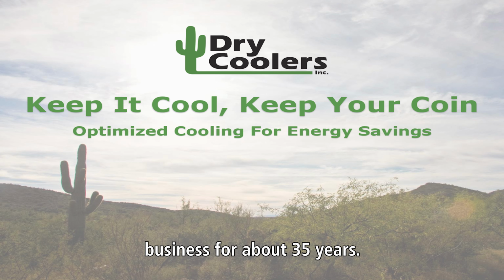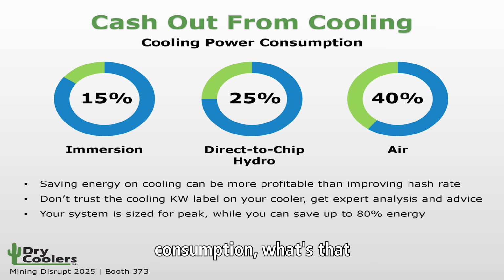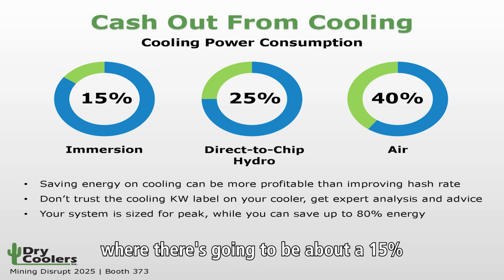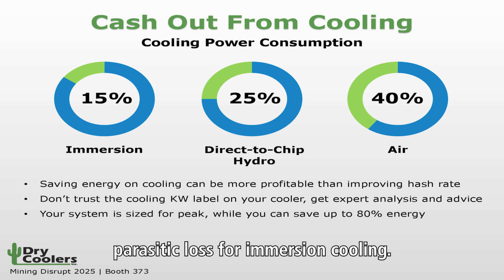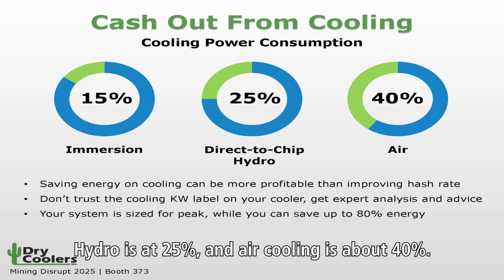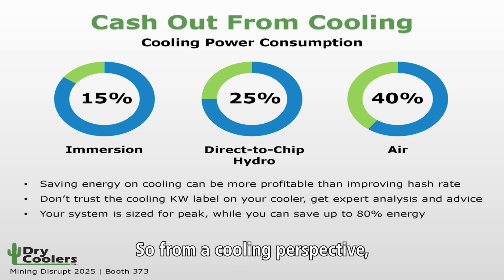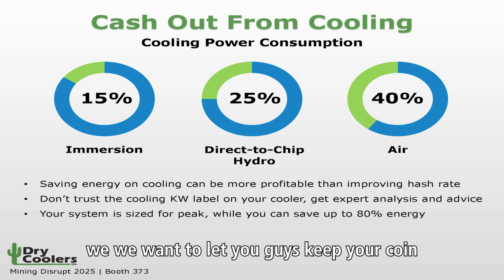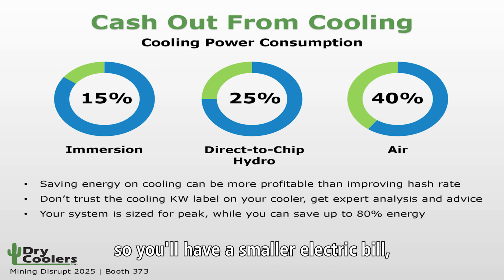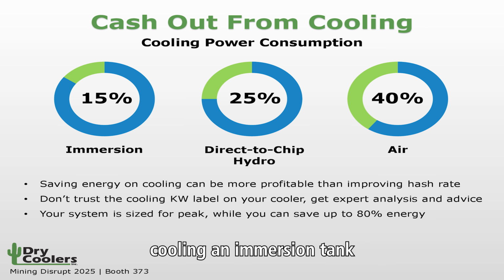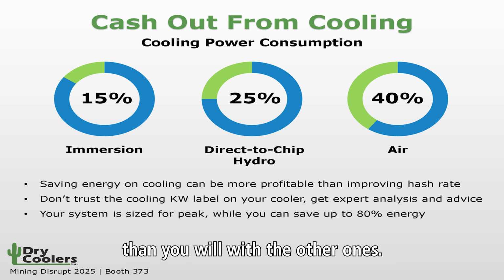First, let's look at what type of power consumption, the parasitic cost of your cooling. Our research shows that immersion is the most efficient, with about a 15% parasitic loss for immersion cooling. Direct-to-chip hydros is at 25%, and air cooling is about 40%. So from a cooling perspective, if you ask the cooling guys what they want to cool, we want to cool immersion. We want to let you guys keep your coin, so you'll have a smaller electric bill cooling an immersion tank than you will with the other ones.